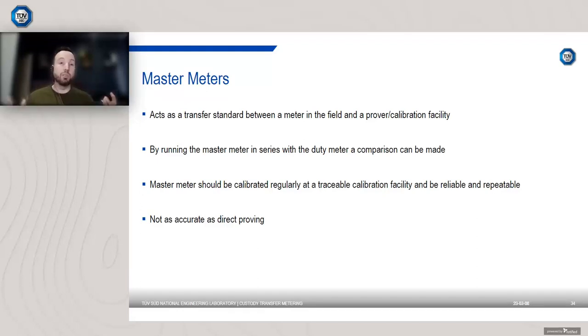Usually a master meter is a lot more compact. So if you've got an installation where it's not practical to deliver a full-size prover on the back of a truck, for example, a master meter is going to be a much more compact solution. Key considerations with any master meter are it needs to be reliable and repeatable, so it needs to have been calibrated or proved at a traceable calibration facility, for example.